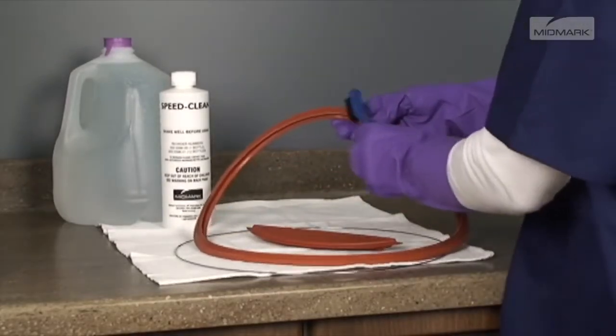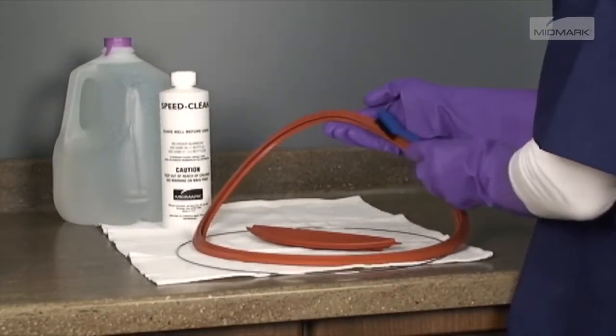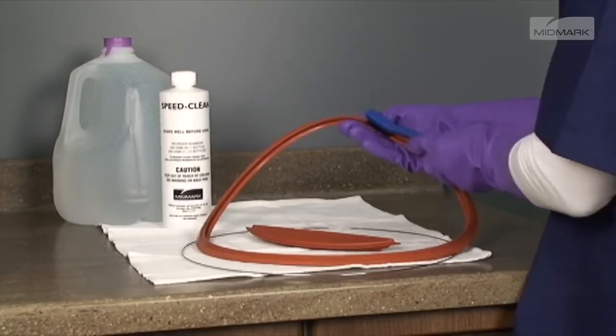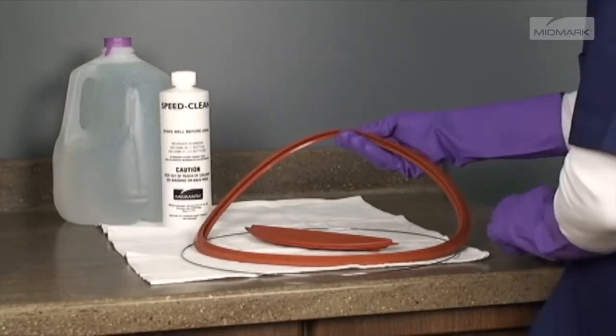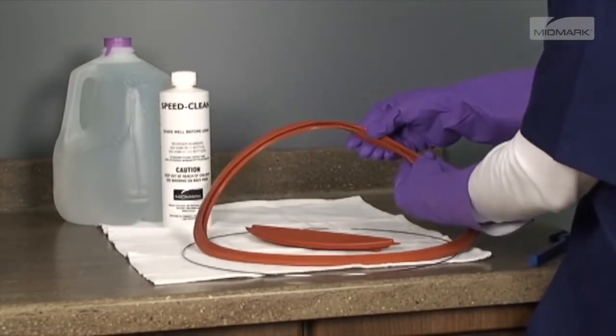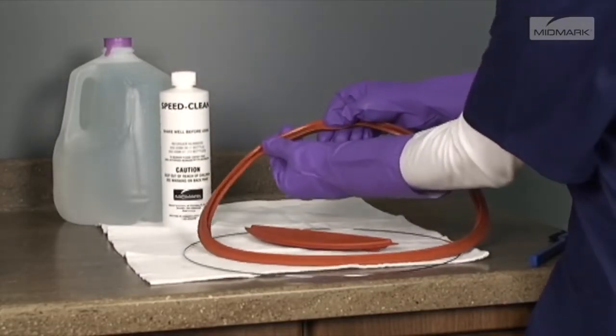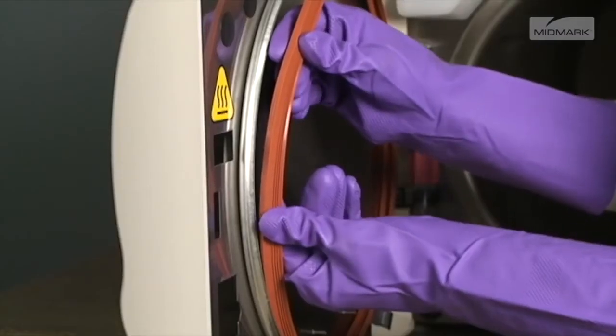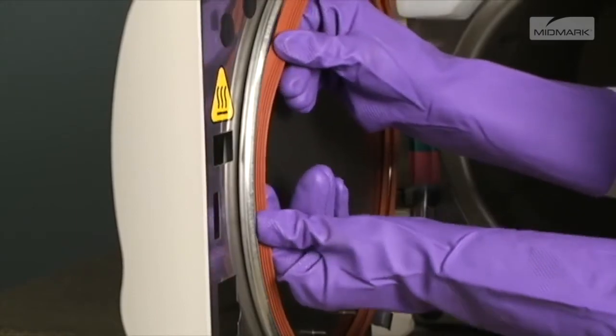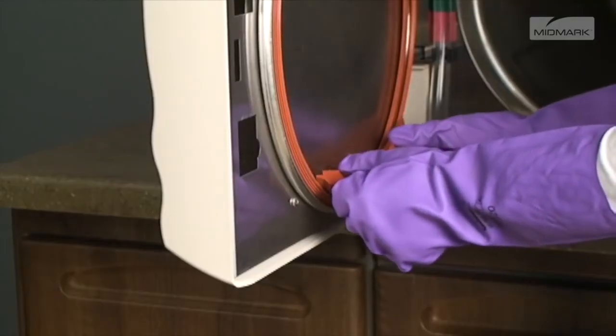Clean gaskets and ring with Speed Clean, distilled water, and a soft brush. Inspect the gaskets for damage, shrinking, or swelling. Replace the gaskets if damage is apparent. Press the door gasket ring into the channel in the door gasket and place the door gasket back into the door. The next part of the required monthly maintenance involves verifying proper operation of the pressure relief valve.